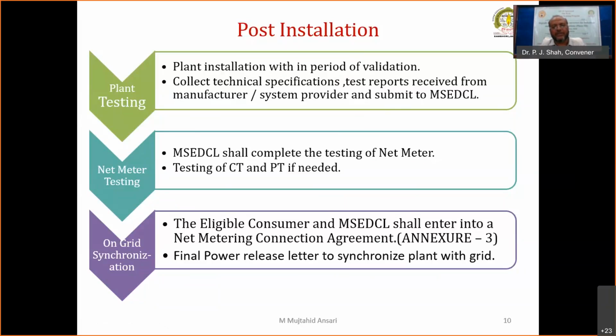If you submit to the MSEDCL, they will grant permission and send a release letter, as it's called in Maharashtra. MSEDCL shall complete the testing of net meters. If the net meter is new, we have to conduct the test and collect the certificate from MSEDCL as well as the manufacturer.